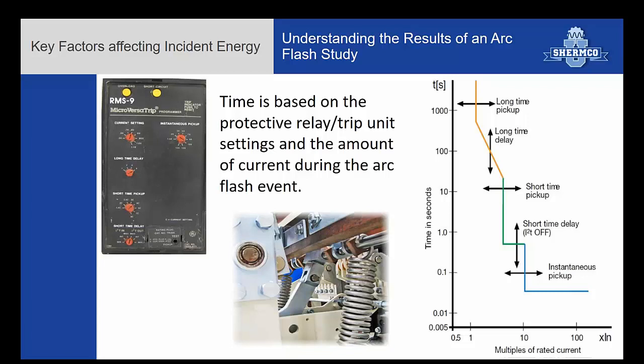But when we talk about time, we're really talking about a very small amount of time in most cases. So equipment performing correctly, having good testing and maintenance done on equipment, a breaker or switch opening slowly can greatly affect that 0.05 to 0.3 seconds that we're typically talking about. So maintenance is very important. All the study is based on time, that everything's working correctly, and the longer the time, the higher the exposure. So this is typically done through relay settings or breaker settings or fuses.